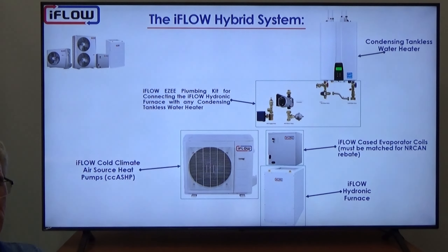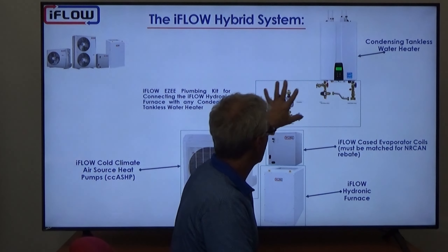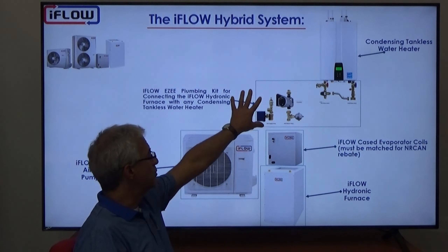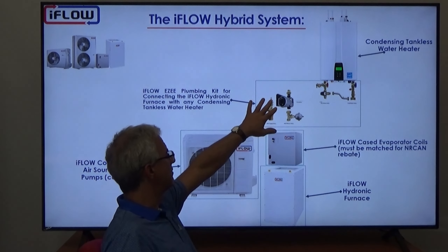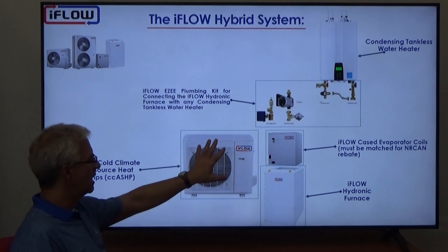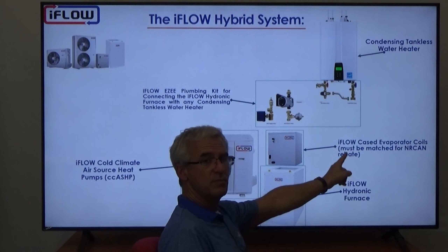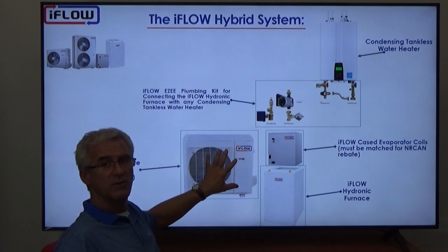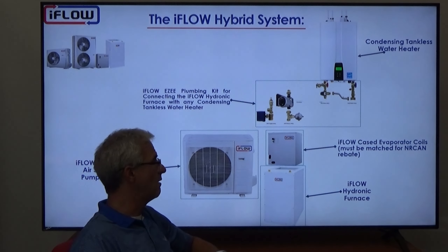This is the iFLOW hybrid system: a condensing tankless water heater as the gas source, connected to the iFLOW hydronic furnace via a plumbing kit that makes everything simple and easy. The kit includes an isolation valve kit, pump, expansion tank, two-way valve, and air vent — all potable rated. Then we have the cold climate heat pump with the outdoor unit and matched evaporator coils. For the Canada Greener Homes rebate of $5,000, you need a matched pair, so you may need to change the evaporator coil as well as the outdoor unit.